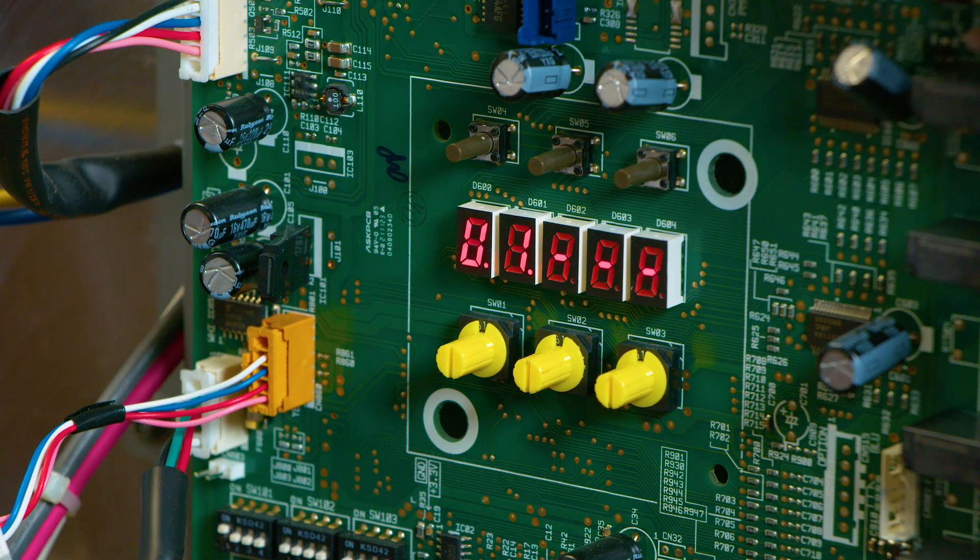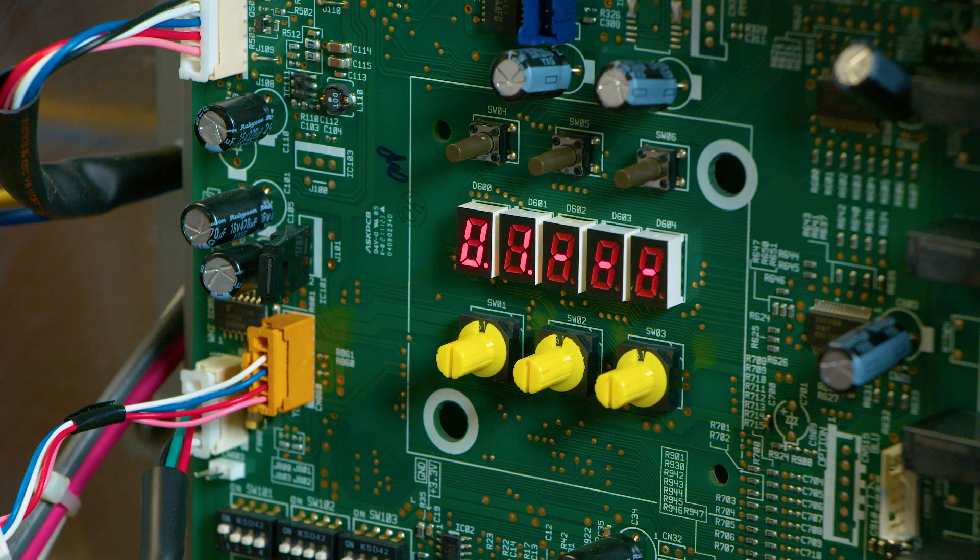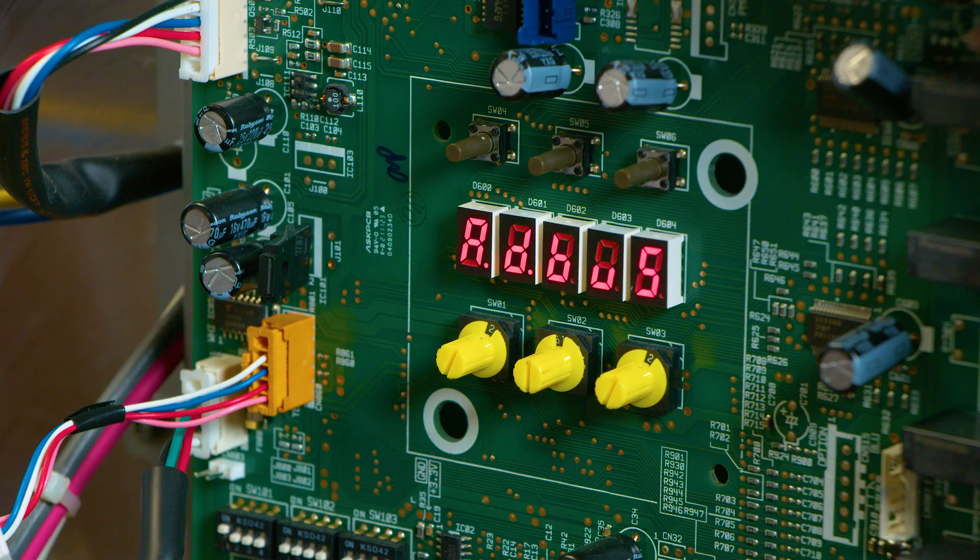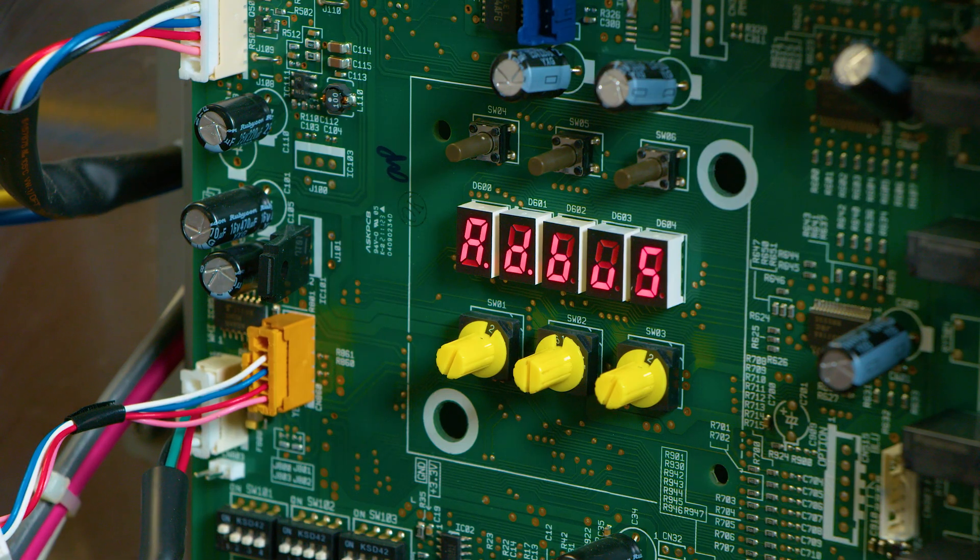With the display and dials now located, we first need to clear any existing addresses. We can do this by placing the dials to 2-1-2. With the dials placed at 2-1-2, we expect to see ADBUS populate on the LED display.